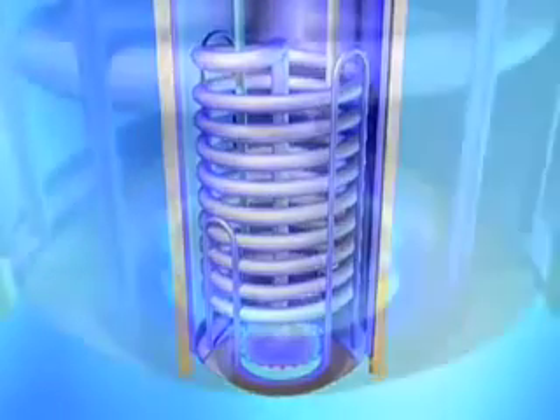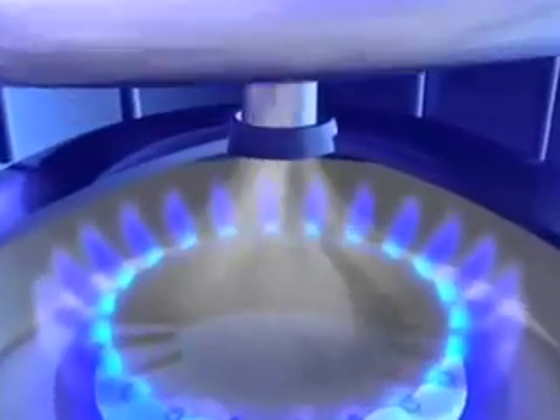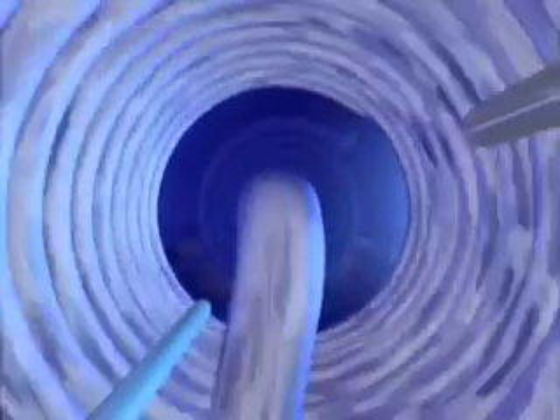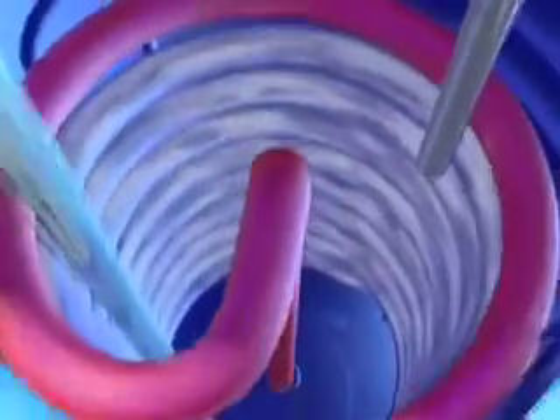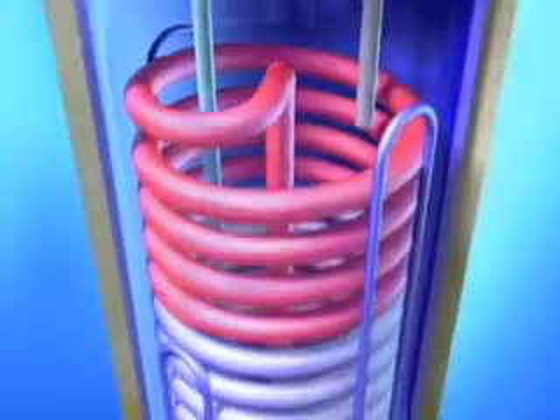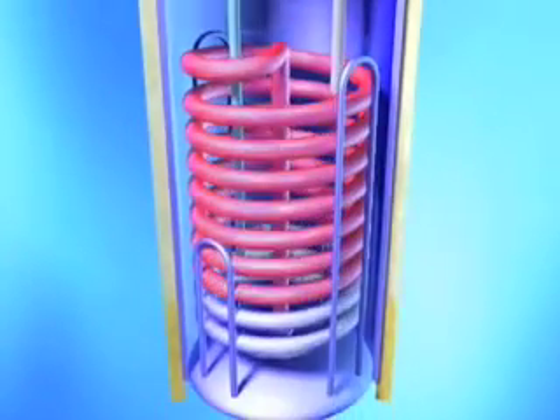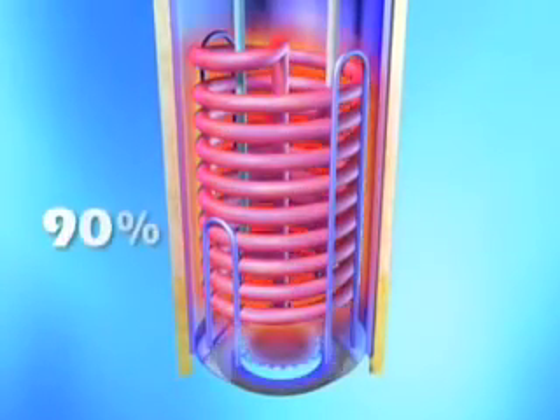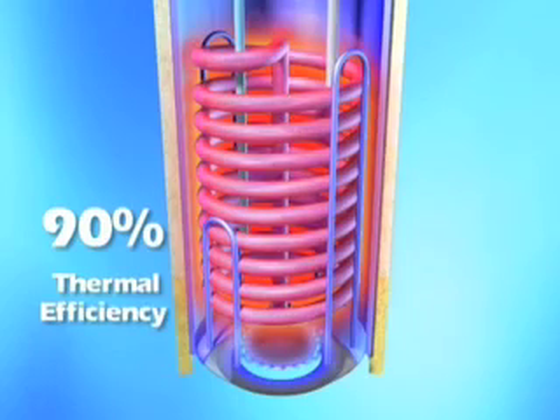Instead of simply going straight up and out, as in a standard water heater, in the Vertex, hot gases are drawn up, around and down through a glass-lined helical coil heat exchanger made from low-carbon steel. The Vertex boosts thermal efficiency to 90% because the coil dramatically increases the total amount of heat transfer surface and keeps the hot gases inside the water heater longer.